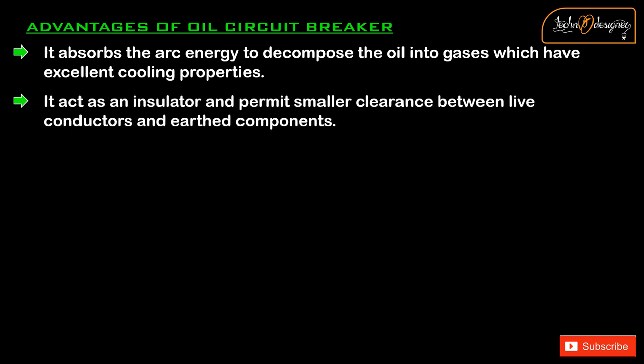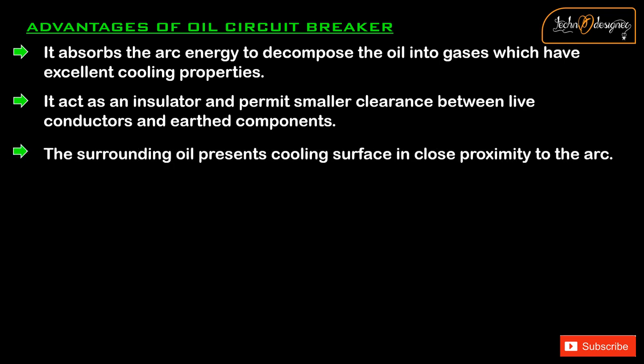Advantages of oil circuit breaker: It absorbs the arc energy to decompose the oil into gases which have excellent cooling properties. It acts as an insulator and permits smaller clearance between live conductors and earthed components. The surrounding oil provides a cooling surface in close proximity to the arc.